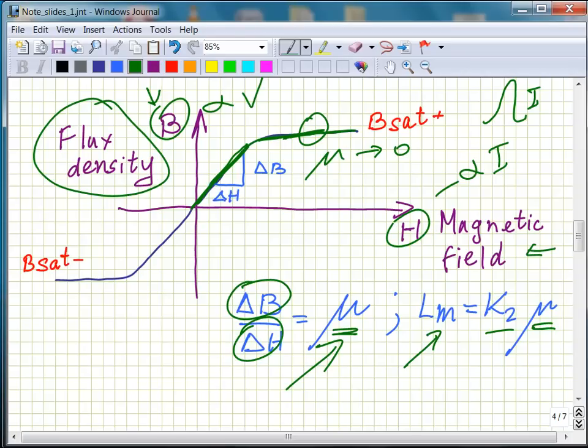The reason is that this high current is actually pressing or causing the core to be compressed due to the magnetostrictive phenomenon. So, the conclusion is that in normal operation, you'd like to confine yourself to a given region of this curve from here to here and be below the saturation region.